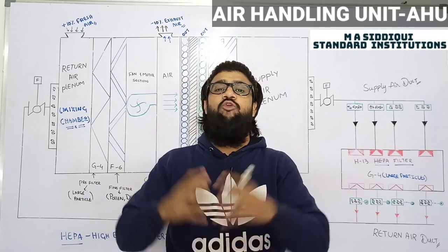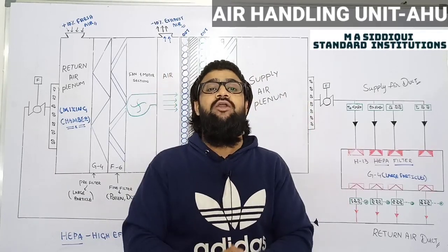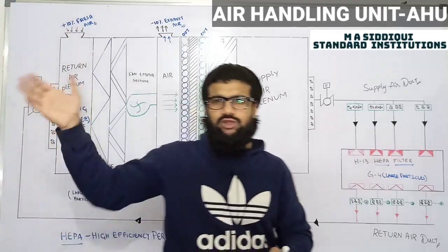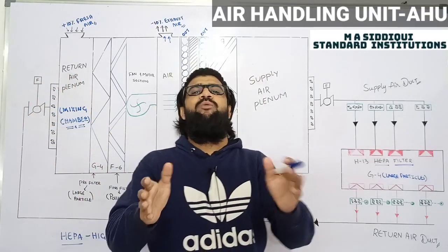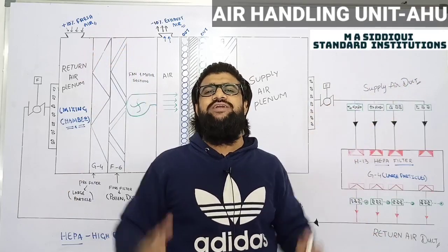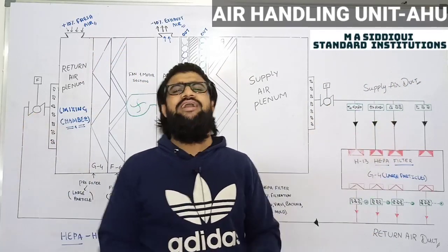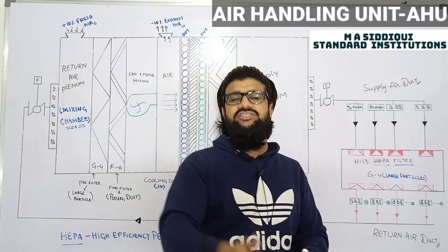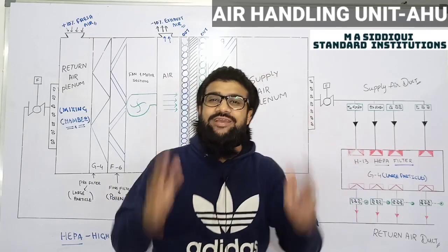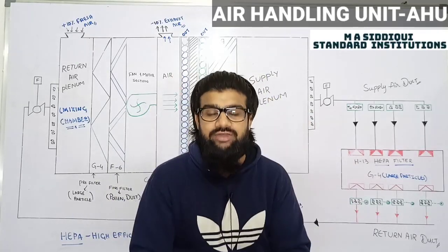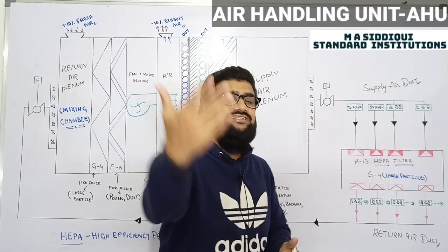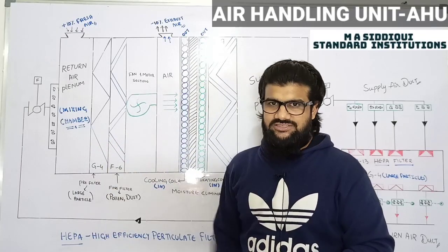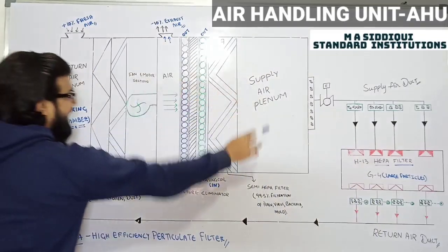Not just multiplex, for banquet halls, for seminar halls where there is a huge gathering, there is definitely no need to keep on giving many FCUs, fan coil units of little capacity. Let's provide 1 or 2 air handlers for a huge space with only ducting, it will be doing the task. So be clear, for 2 BHK, 3 BHK flats, we will be using fan coil units. For big spaces, as in function halls, banquet halls, seminar halls, as in screen 1, screen 2, screen 3 of all the multiplexes and theaters, it's better to go with air handlers.